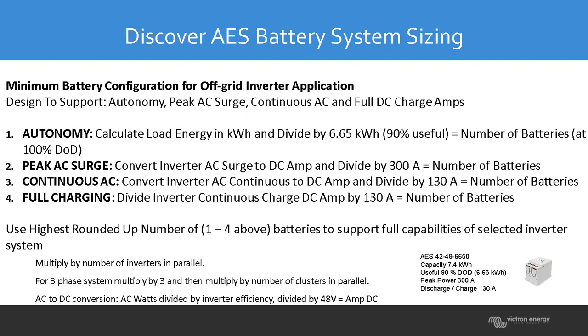And for peak AC surge, convert inverter AC surge to DC amps and divide by 300. So that's the maximum charge that you can put on those batteries. For continuous AC charge, convert inverter AC continuous to DC amps and divide by 130. So 130 amps is a continuous that you can get out or put in those batteries. I will share my slide deck, and this one's kind of busy, but basically this would give you a good way to size a Discover battery to your Victron gear.